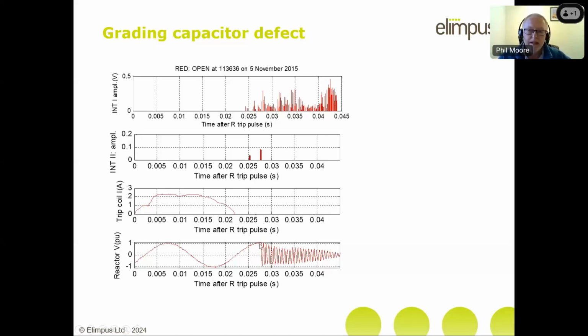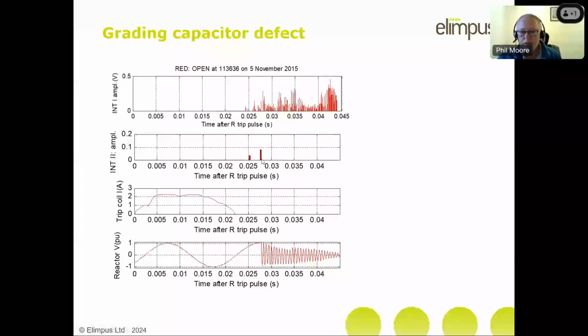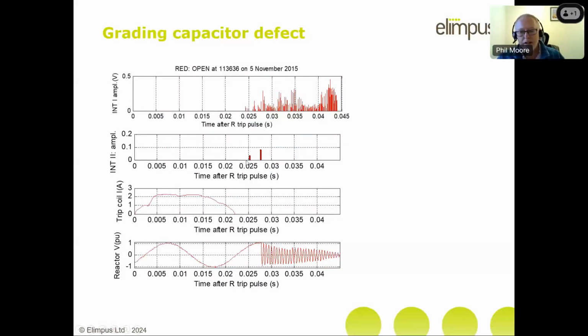Back in 2015, we were actually measuring the radio frequency emissions from both breaks of the interrupter, both the left and the right hand interrupter. I've referred to these as interrupter 1 and interrupter 2 in this particular slide. So you can see here the arc has gone out at about 27 milliseconds after the trip coil. At 27 milliseconds, interrupter 2 had a couple of impulses. This is just showing you the peak value of the impulse. It doesn't show you the waveform. So it shows a couple of impulses there.